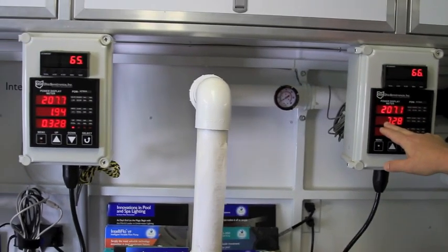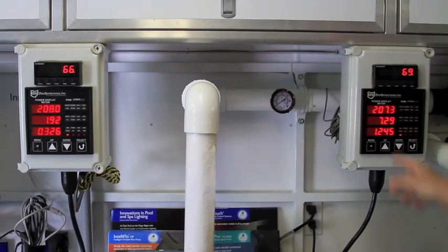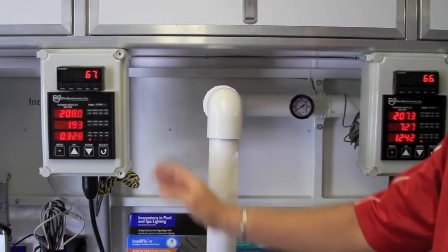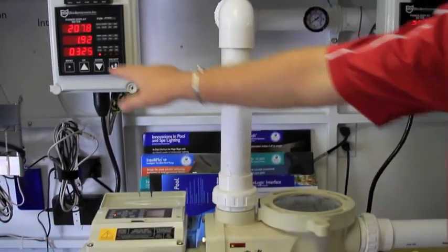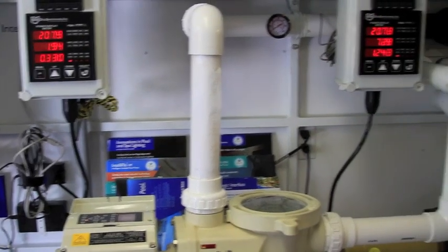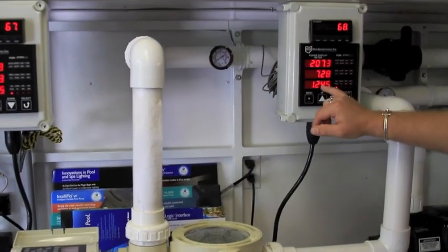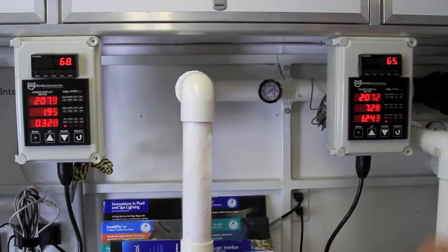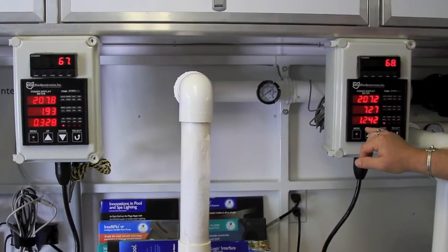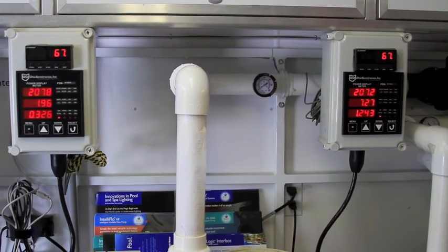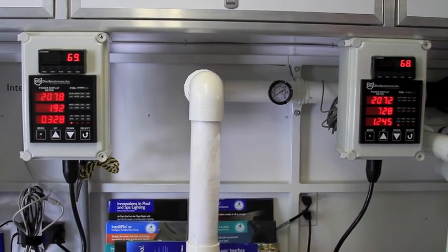Our amp consumption on this standard efficiency pump is upwards of 7 amps. Our IntelliFlo here is running at the same rate. It's about 1.92. And this last line to show a comparison is the true money line. This is what your power bill is based on, kilowatt hours.